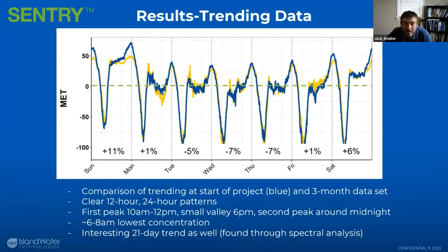And you can also see, all right, what is the pattern at this location? You can see, this is Sunday to Saturday, so this is a weekly. You can see the Sundays and the Saturdays for this location is historically higher. You can see the loading's a bit lower during the midweeks, Tuesday through Thursday, with Monday, Friday being average. Again, green being the average loading.